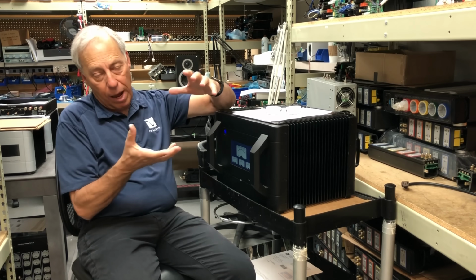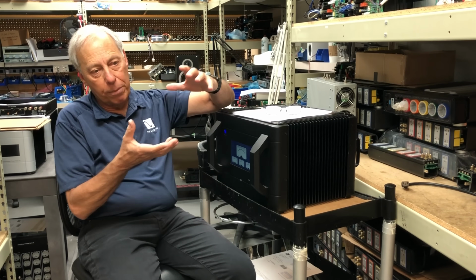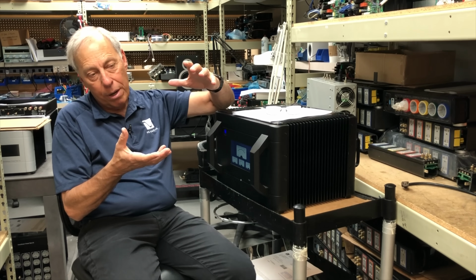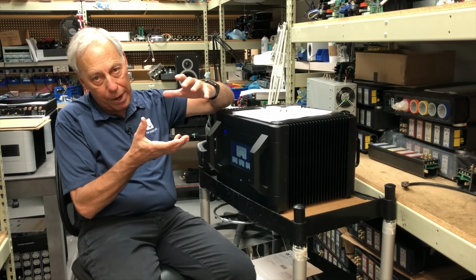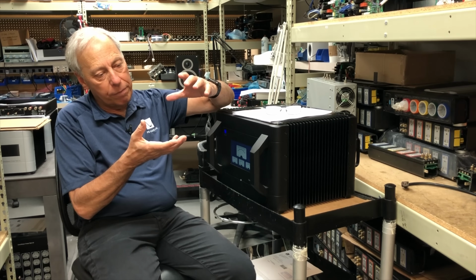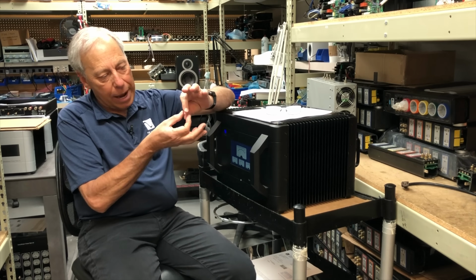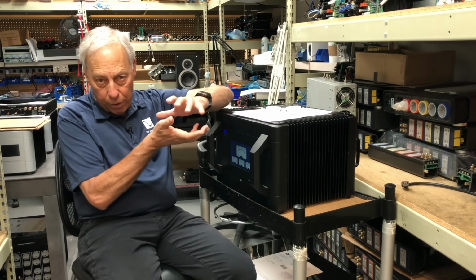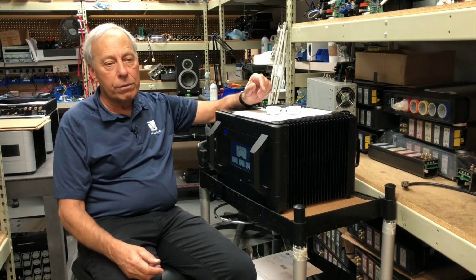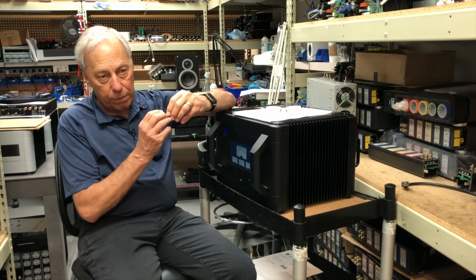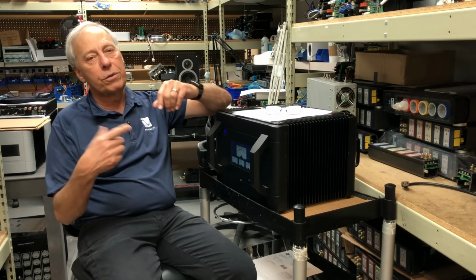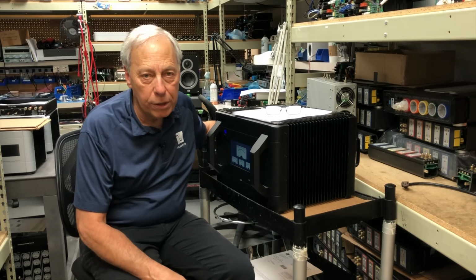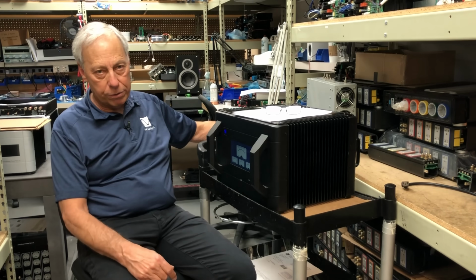And the opposite is true - transformers in Europe are 10-20% bigger than transformers need to be in the U.S. Very small transformers happen when you have higher frequencies. So a 400 hertz transformer is very small relative to a 60 hertz one. We'd save a whole bunch of copper and iron by having 400 hertz transformers.